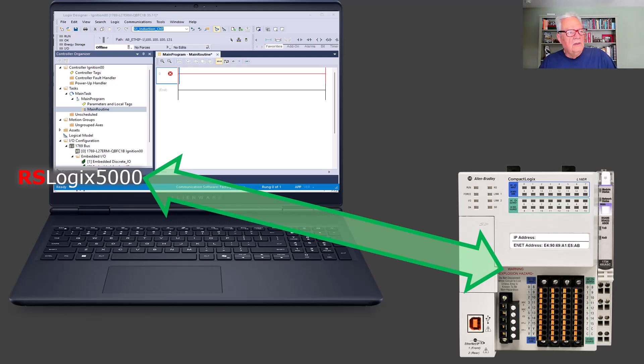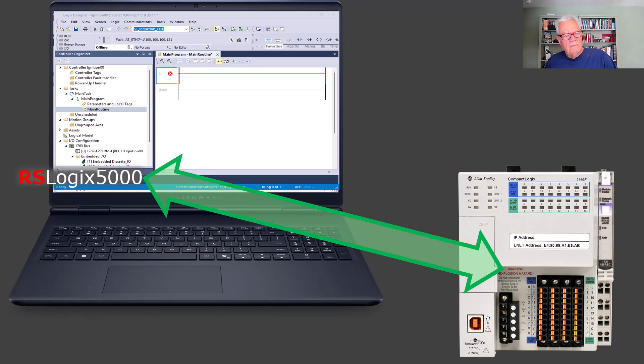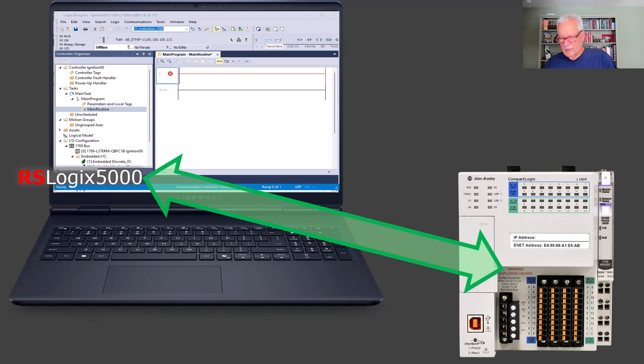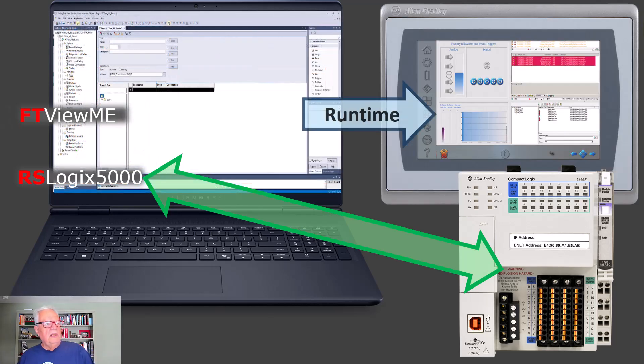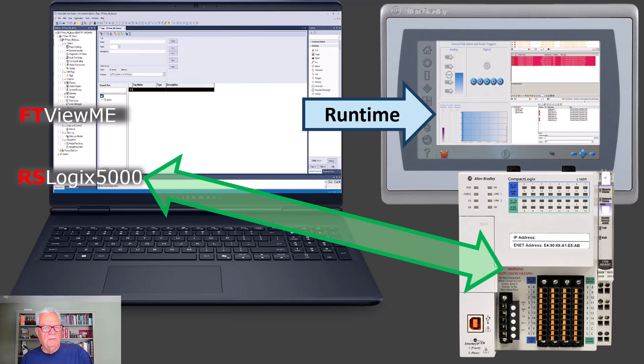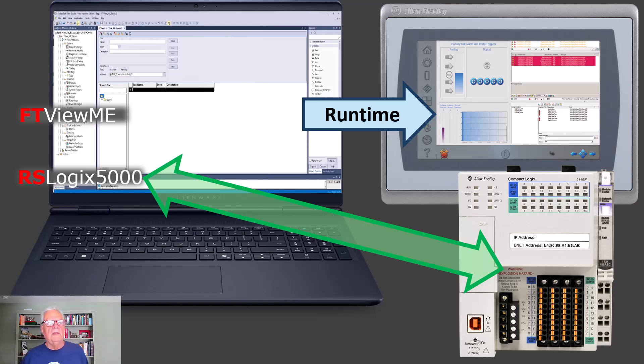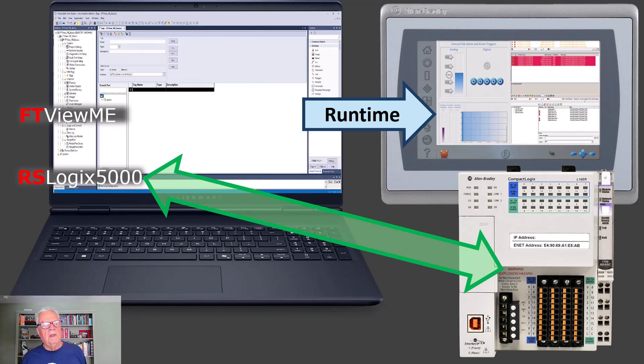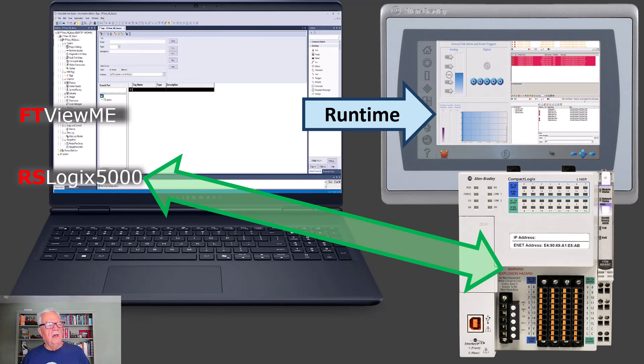As long as the person doing the Panel View has the I/O list from the person doing the PLC programming, and the general idea of the process, they can get started on the HMI before the actual program for the PLC is finished. Then you need to pick a Panel View, a specific model, open up Factory Talk View ME, configure it for that specific proprietary piece of hardware. Then in Factory Talk View ME, you create a runtime and you download it to the Panel View.